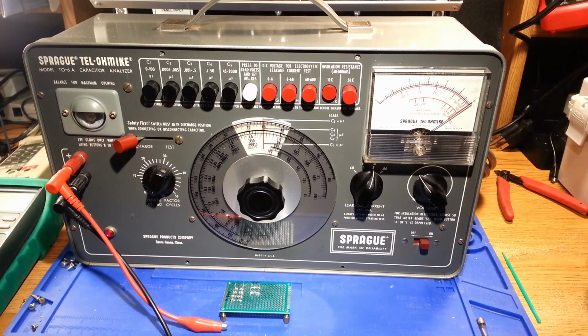In this episode I am going to go over measuring conductance or high resistive values using a couple of devices you might have or might be able to get availability to or create for yourself. One of the things that you find out about working with most multimeters is they only can measure up to a certain range of megaohms of resistance, somewhere usually between 40 to 60 megaohms, maybe 100 megaohms at the top end of the range.